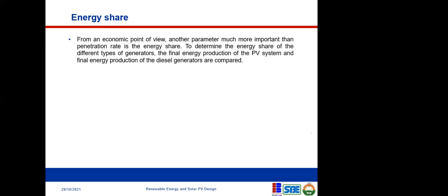So you have a diesel generator system and a solar PV system. At the end of the day, you compare the energy that you've collected from the generator and the energy that you've collected from the solar system. That is what we call energy share. Out of the 100% energy consumption, what percentage came from the solar system and what percentage came from the diesel generator.